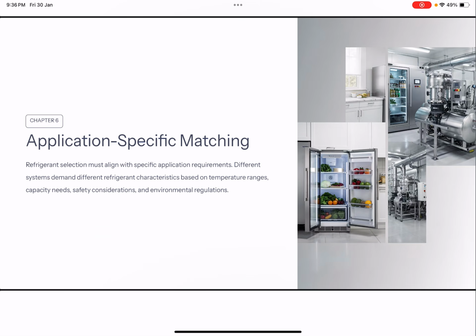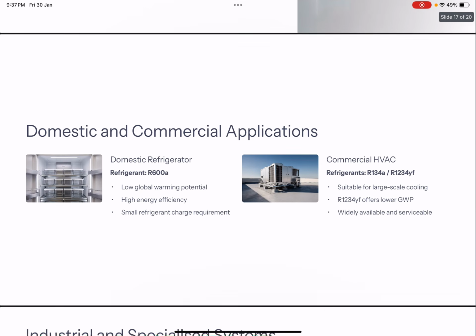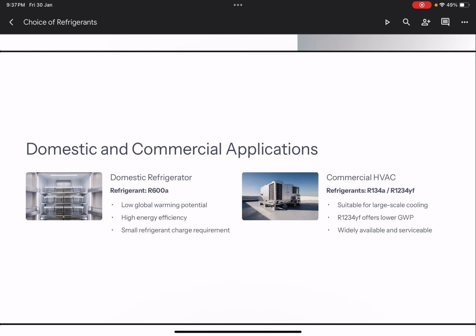Refrigerant selection must align with the specific application requirements, because, as I said, the evaporation temperature has to be mapped with the temperature at which the system has to be maintained. For example, household refrigerators we need to maintain at lower, negative temperatures. Ultra low temperatures are in ULT systems. In air conditioning systems, relatively higher temperatures are required. These are some typical refrigerants which are widely used. Domestic refrigerators: R134a or R600a. Commercial HVAC systems: R134a or R1234yf.